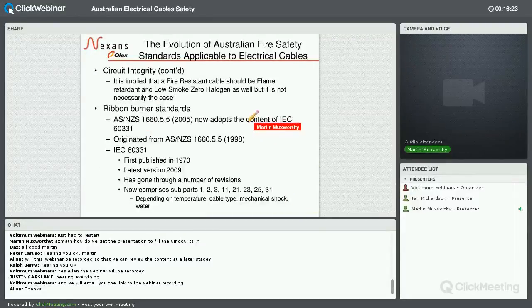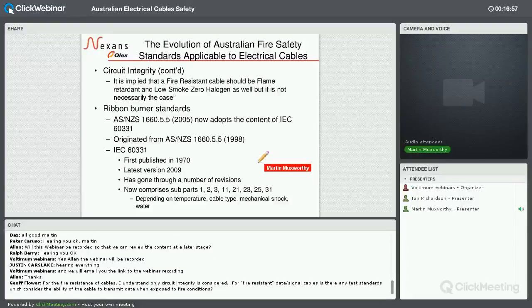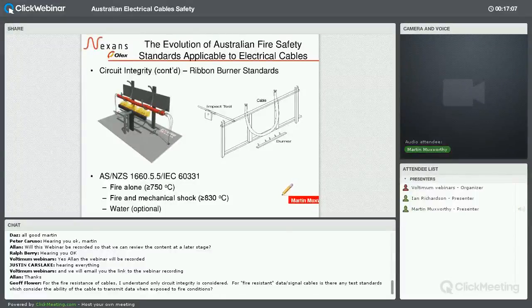In the case of the ribbon burner standards, covered by 1660 Part 5, and as I mentioned, this one actually adopts the entire content of the IEC 60331. We go back to quite some time when 60331 was first developed, which was first published in 1970. So again, an indication that these standards have gone through a fairly rigorous period of development and have established themselves in the industry. The next few slides discuss how the test is actually conducted. And there's a number of elements to this ribbon burner test as I've described it.